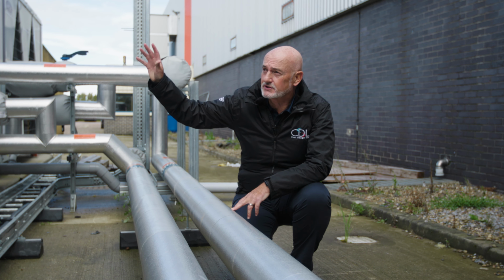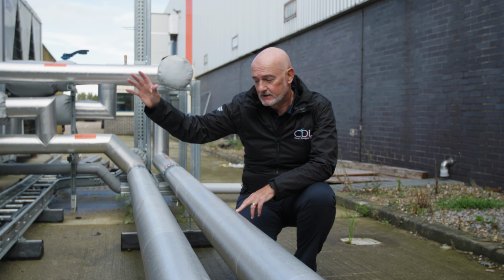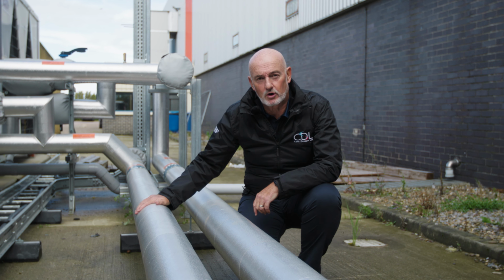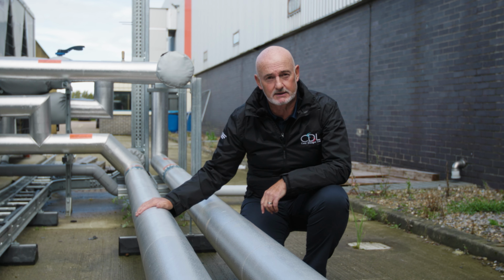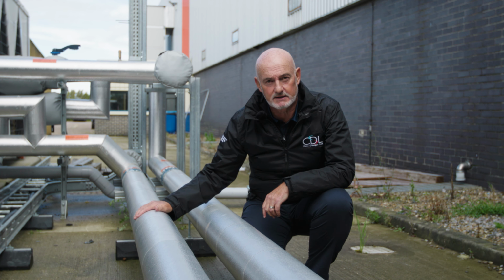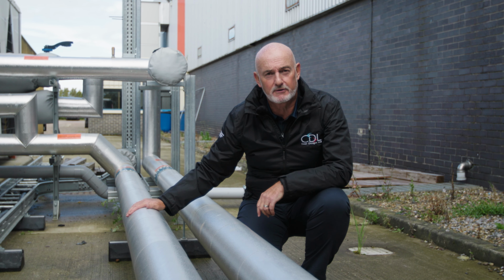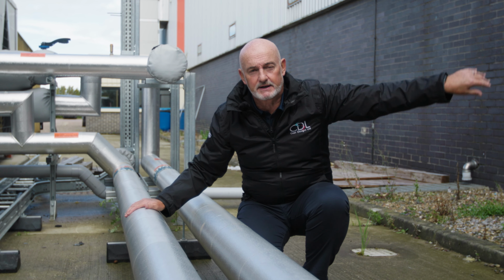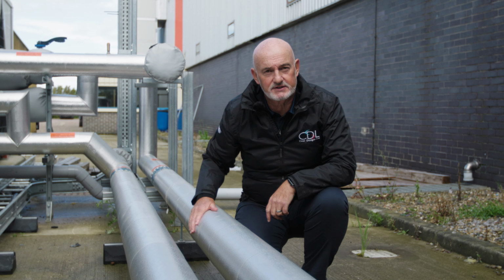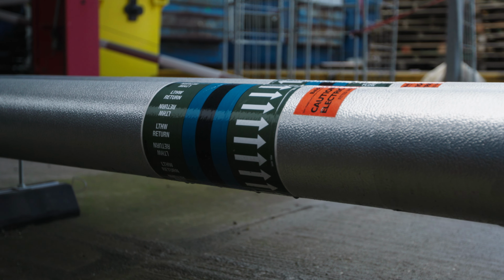Okay, so once the air source heat pump machines have absorbed the heat, they put it straight into the water. Here, this is the flow on this particular job. The flow is 48 degrees C. Off it goes to do its job, off to the buffer. When the heat's been dissipated into the warehouse, it comes back, and on this occasion comes back at 38. So the water comes into the machines at 38 degrees C, and it goes out at 48 degrees C. These machines will operate down to -5 to create this water at 48 degrees C.